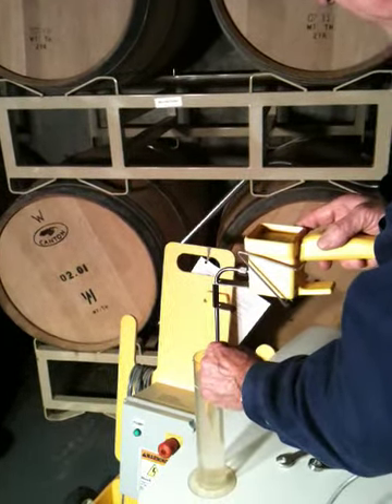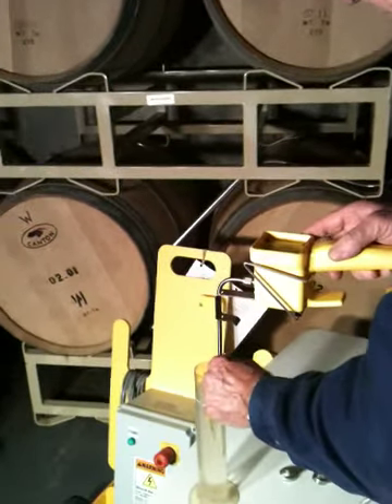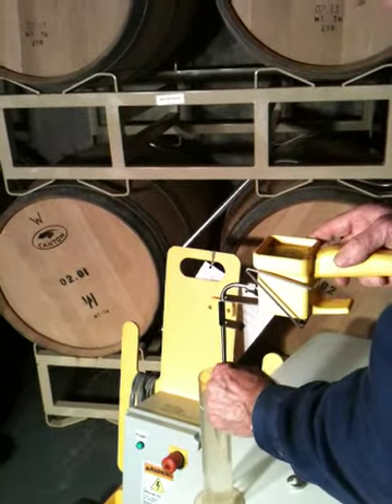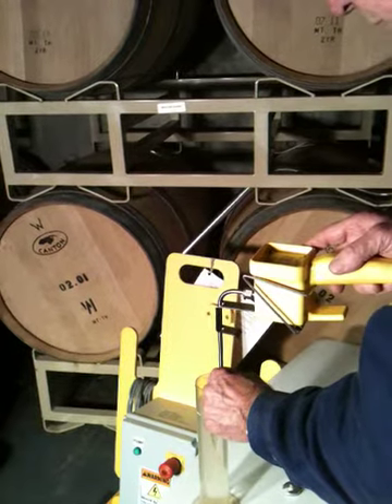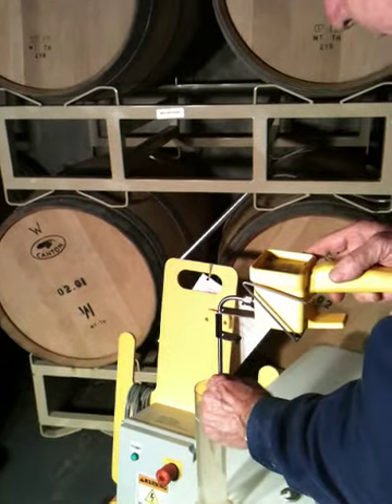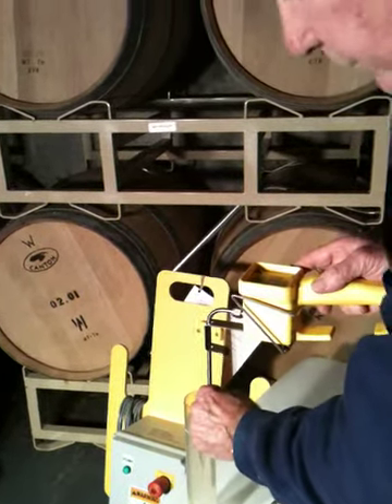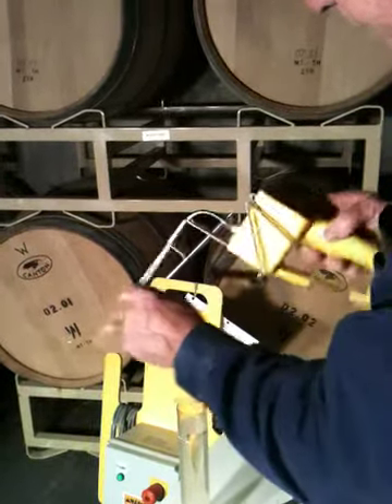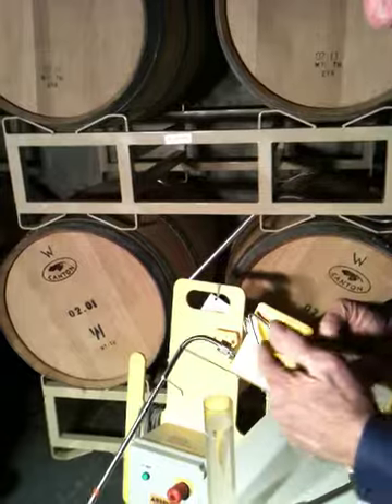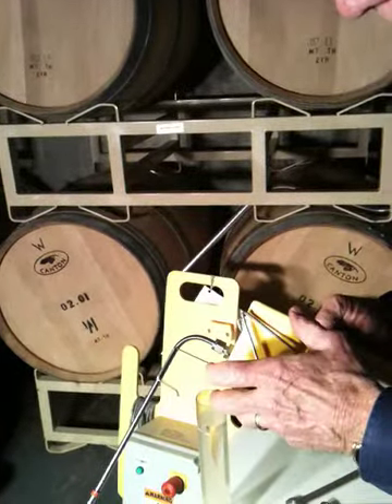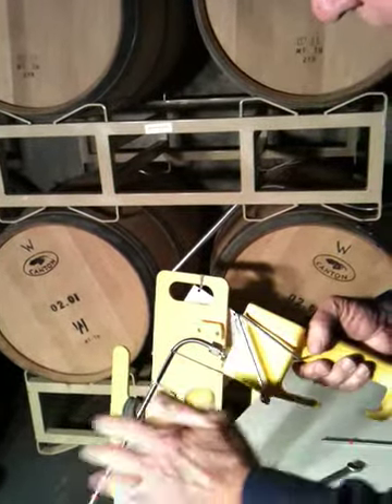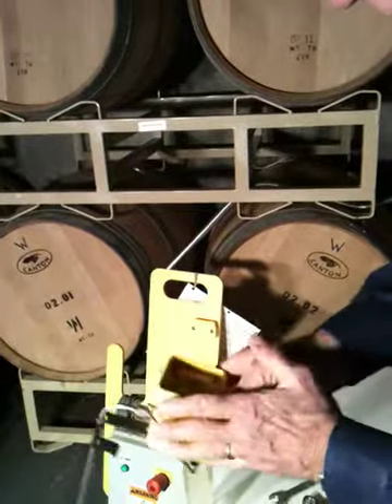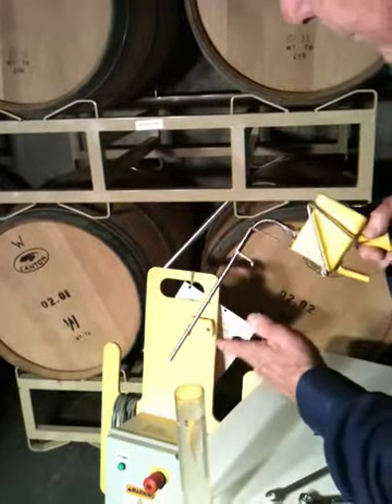It's doing this for approximately 10 seconds. If it passes the leak test, it'll flash green real fast, which it's doing right now. So we've just passed the leak test. If it were to flash red very rapidly, it means we have a leak still. And it's recommended then to go back and tighten this nut again. That's really the only source. Now, it can have an internal leak, but if it has an internal leak and you can't clear it from the outside, then you'll have to ship the handheld controller back to the factory for repairs.